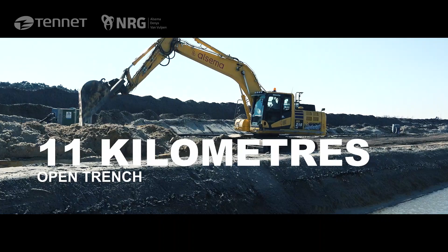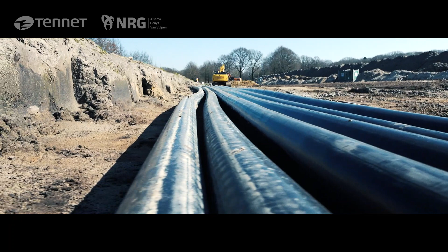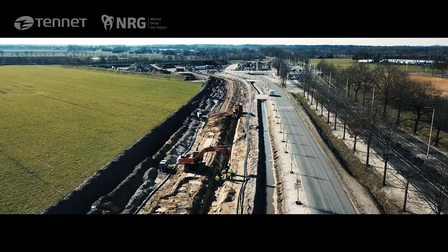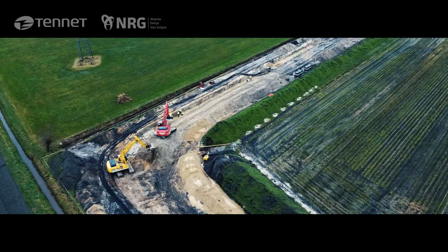An open trench was dug over a length of more than 11 kilometers in which 2 150 kilovolt connections were laid. When laying cables in an open trench, you need to lower the groundwater level. NRG used the zip method to minimize the amount of groundwater that needed to be pumped up. This is an installation method devised by NRG that has proved to work well.